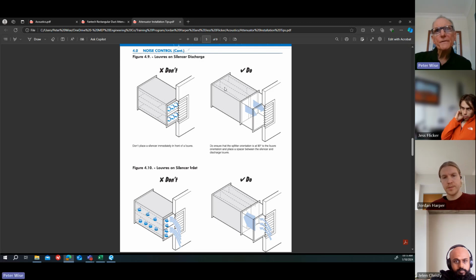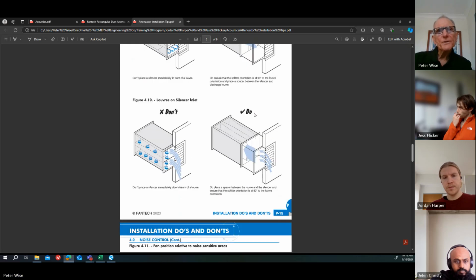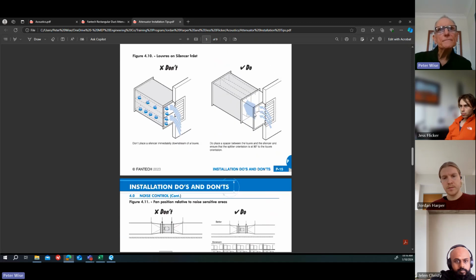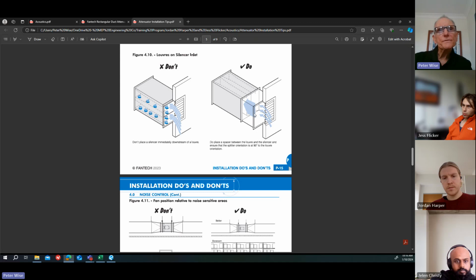The best way to do it is to have vertical splitters and create a spacer duct again. Let the air straighten out before it hits the louver. It's all common sense sort of stuff, but it's worth taking note of if you're designing things to make sure it's going to work properly, because I've seen lots of jobs where, say, a consultant designs something and he's putting attenuators right on a bend or right on a branch and they just don't work. You can't do it that way.